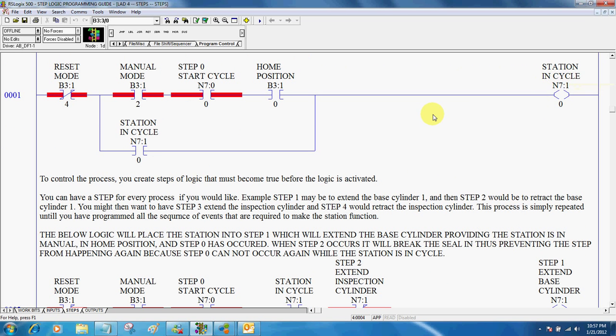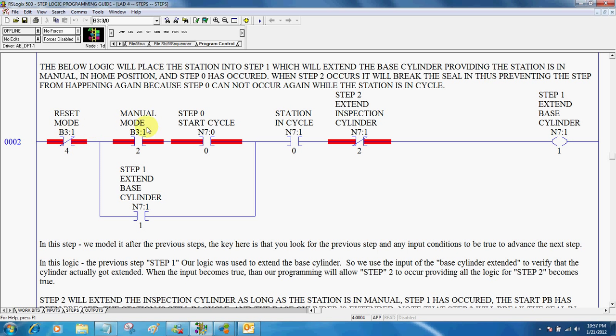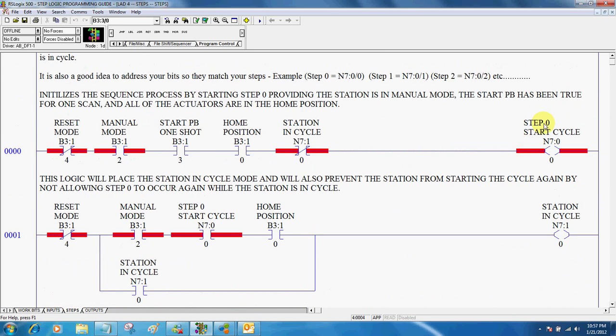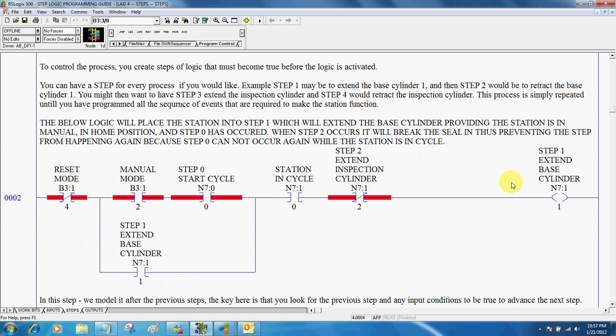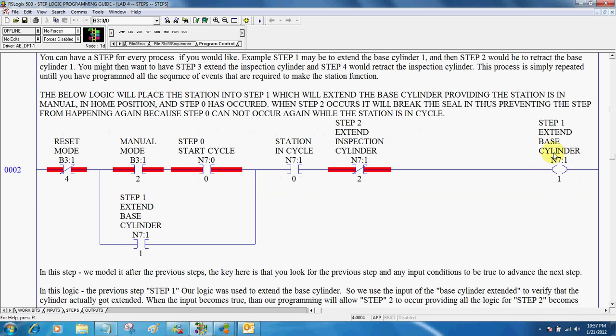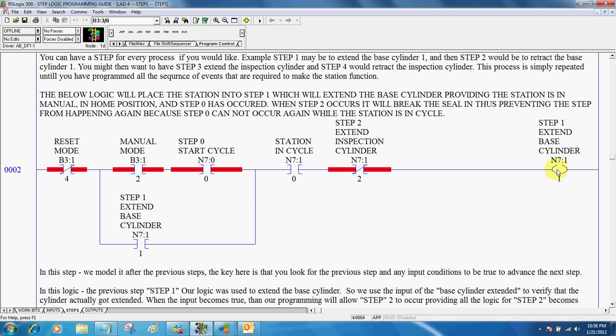So remember, we're station in cycle. So now we want our manual mode, step zero to occur. Station is in cycle. And as long as step two hasn't occurred, step one will begin. So really, these first two steps are kind of like some precursor steps to get things started. And this is our very first step of our program. So step one basically says, I want the station in manual mode. I want step zero to have happened. I want it in cycle. And as long as step two hasn't occurred, I will allow step one to activate. When step one activates, it also creates a seal in and maintains that step one on.